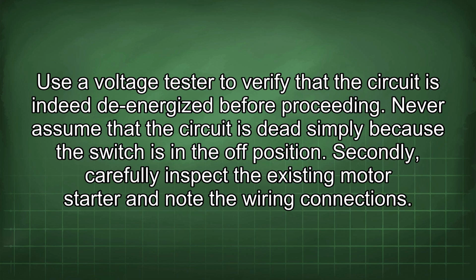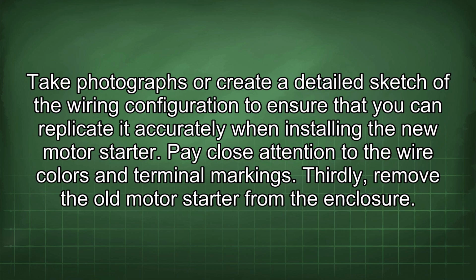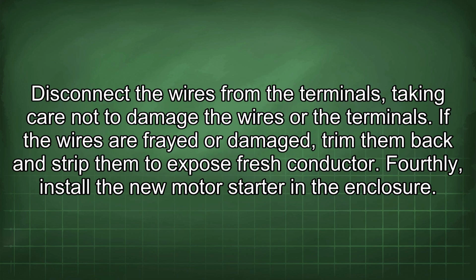Secondly, carefully inspect the existing motor starter and note the wiring connections. Take photographs or create a detailed sketch of the wiring configuration to ensure that you can replicate it accurately when installing the new motor starter. Pay close attention to the wire colors and terminal markings. Thirdly, remove the old motor starter from the enclosure. Disconnect the wires from the terminals, taking care not to damage the wires or the terminals. If the wires are frayed or damaged, trim them back and strip them to expose fresh conductor.